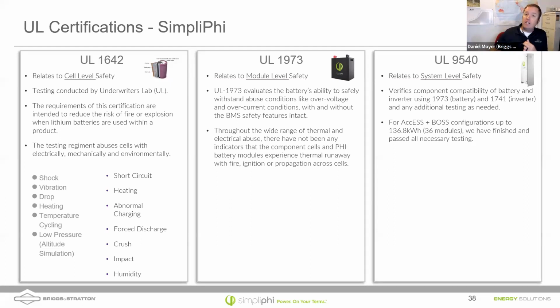UL, so you don't have to believe any of what I just said, because we send the batteries to UL. UL 1642, as I mentioned earlier, is on the cell level, and they put it through a regimen of abusive tests. UL 1973 is on the battery module level. Once we have UL 1973 listed batteries, we can integrate them into a system level with a UL 1741 inverter.